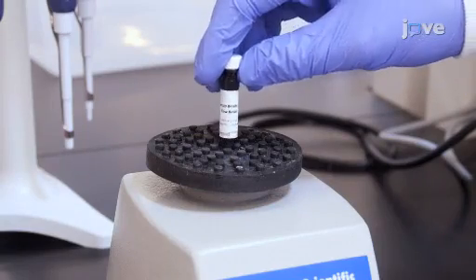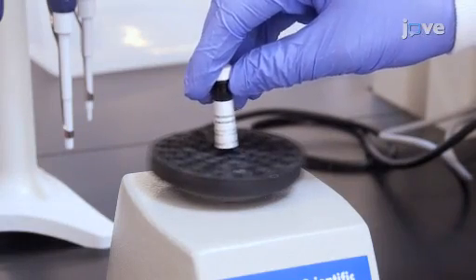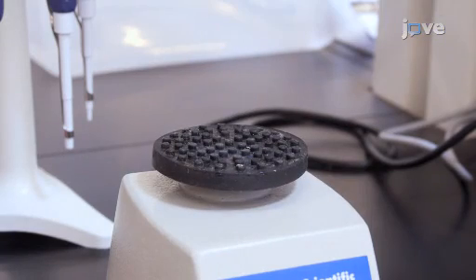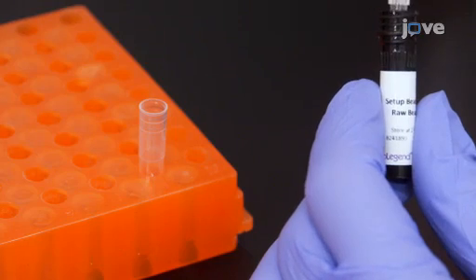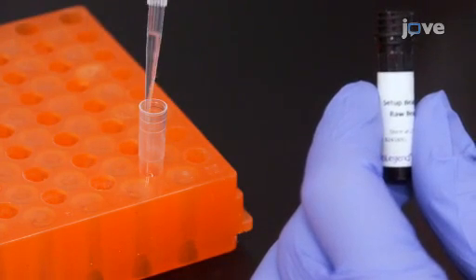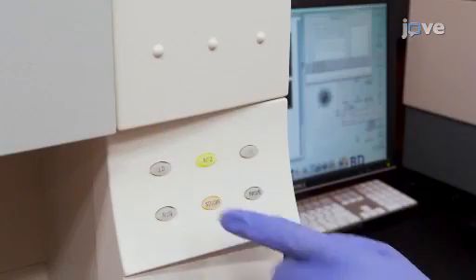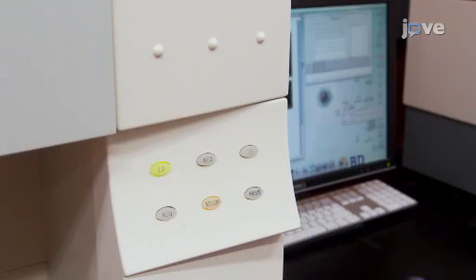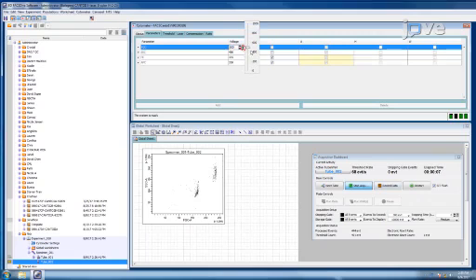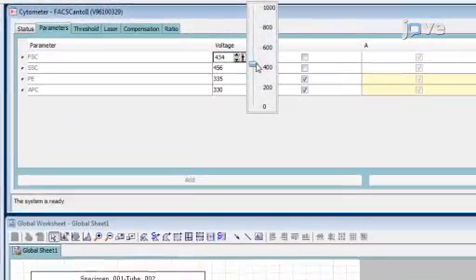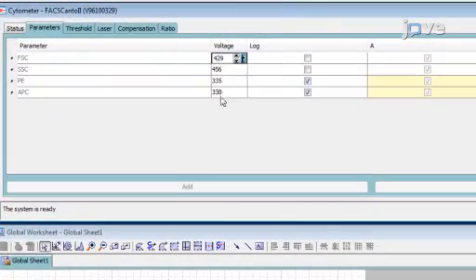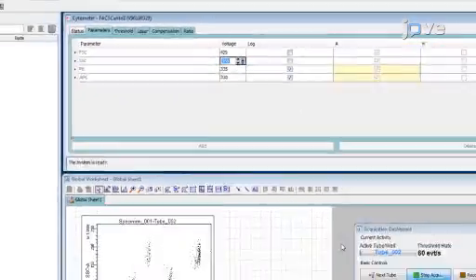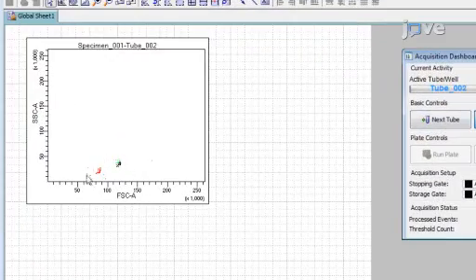Vortex the vial of raw beads included in the kit for 30 seconds to resuspend the beads. Transfer 400 microliters of the raw beads to a new FACS tube. Set the flow cytometer flow rate to low. Run the raw beads, carefully adjusting the gain and voltage for forward scatter and side scatter so that both size populations of these beads are visibly separated and easy to gate.